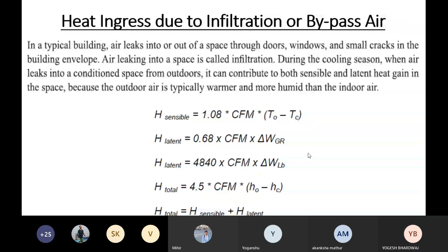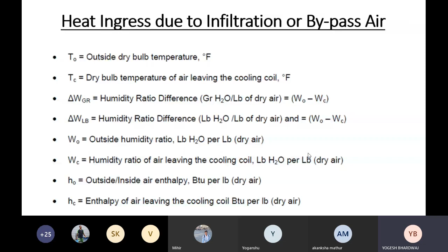So TO is the temperature outside, TC is the dry bulb temperature inside my room or of air leaving the cooling coil. Then humidity difference in grains, humidity difference in pounds. And then HO is the outside air enthalpy, and HC is the enthalpy of air leaving the cooling coil. So now, the earlier equations I gave were for the fresh air which was coming through infiltration. If I'm putting some fresh air intentionally, I put it on the coil.